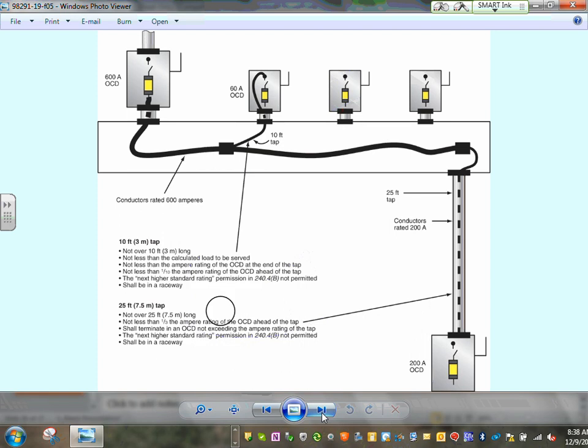Okay, the last thing I'm going to talk about, guys, is the tap rules. I want to bring your attention, guys. I have a 600 amp disconnect that brings it to a gutter. From this gutter, I went to a 60. I have a 10-foot tap. Can you guys see that? That 10-foot tap, and I went into a 60 amp circuit breaker.